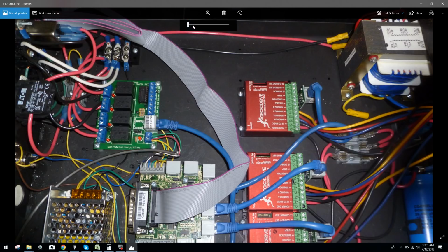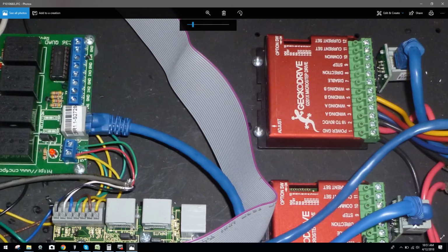Point in reference, let's look right here real quick. We could see a shielded cable here being used with the shield itself exposed, no drain coming off of this, because whoever assembled this system lacked the knowledge and forethought to say, well, the cable is just acting as a cable if we don't have a shield drain actually attached to a ground in the chassis. So therefore, this is essentially just another cable.